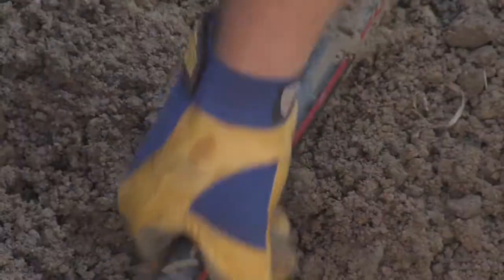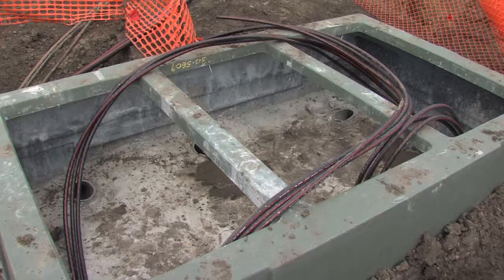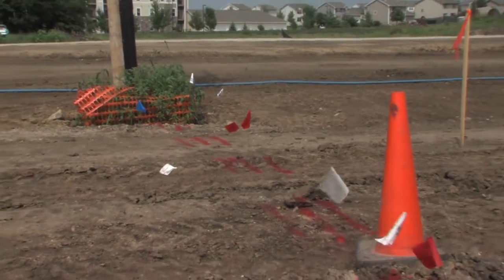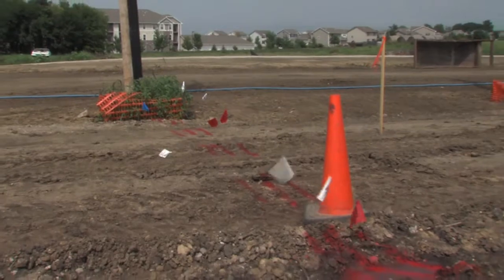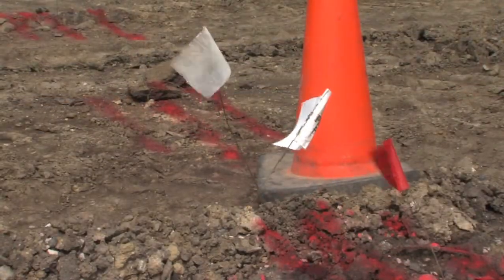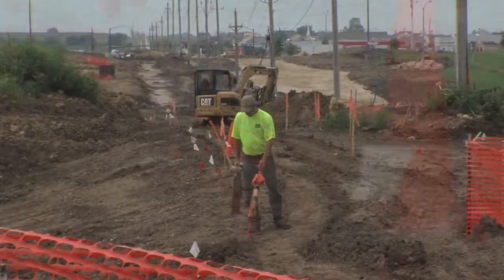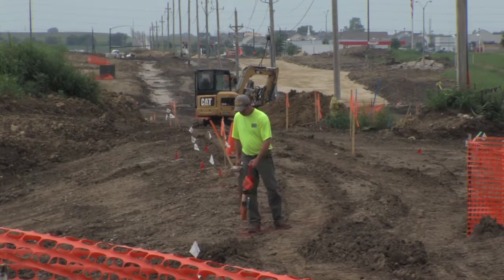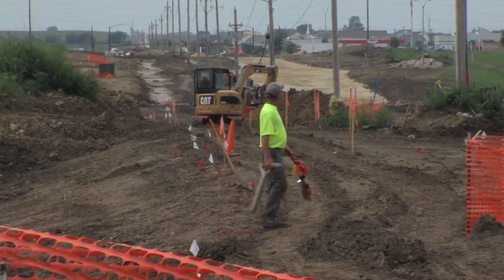Primary cable is buried at 42 inches. The secondary cable goes in at 24 inches at the time of construction. You can never trust those depths due to developers coming in afterwards and changing the grade. On our primary voltages, you could find one cable for a single-phase circuit or three cables for a three-phase circuit. On a three-phase circuit, you cannot trust that all three cables will be next to each other. There could be as much as a foot of separation between each cable. Your locate company should be able to help you determine how many cables are on that particular circuit.